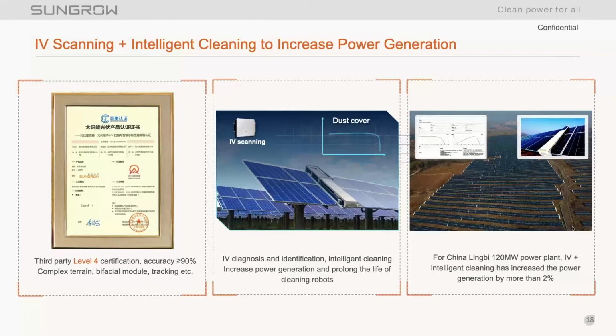And the test site, if we were looking over here at the right-hand slide, this particular 120 megawatt project in China, when it was coupled with the online IV curve scan, the intelligent cleaning, and the predictive O&M, it increased generation by more than 2% from its previous year. Now 2% might not sound like a lot, but when you factor that into the aggregate and extrapolate that over the life of the project, it is significant.